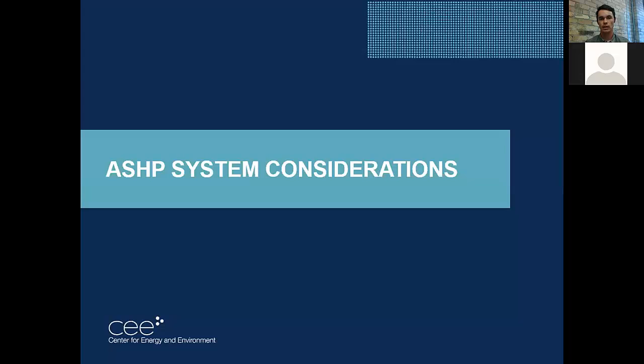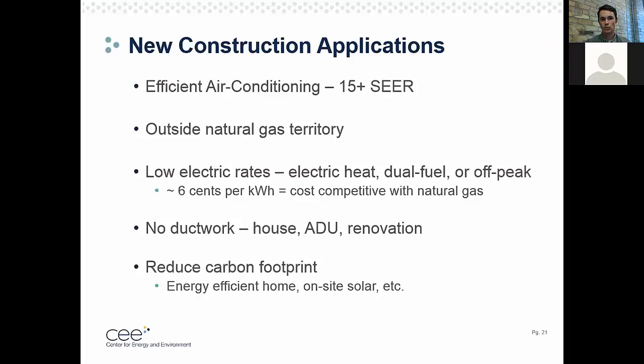So next I'm going to talk about some system considerations when choosing or installing an air source heat pump, keeping it focused on the new construction side. The main application things to consider are these. One thing I wanted to mention is that if you're looking at putting in an efficient air conditioner, simply defining that as 15 SEER or higher, it likely makes sense to install a heat pump. You may not want to pay the extra cost, which we'll get into next, of the cold climate heat pump. But a heat pump with 15 SEER or higher is comparable in price to an air conditioner, and it can be used to deliver heat at those more moderate temperatures, that 30 to 40 degree range that we saw. So it really makes sense to put a heat pump in all homes if you're thinking about installing an efficient air conditioner above 15 SEER.